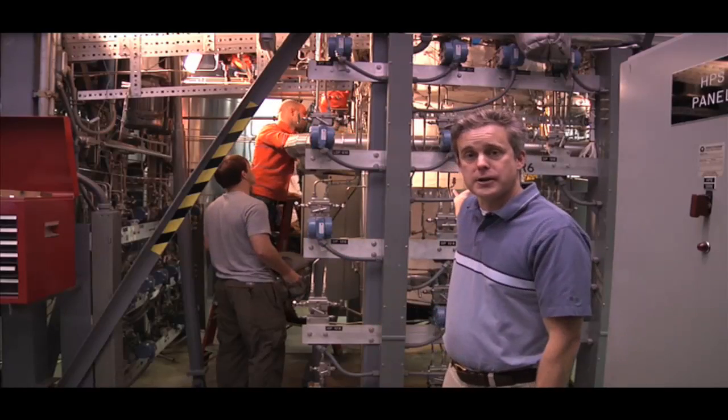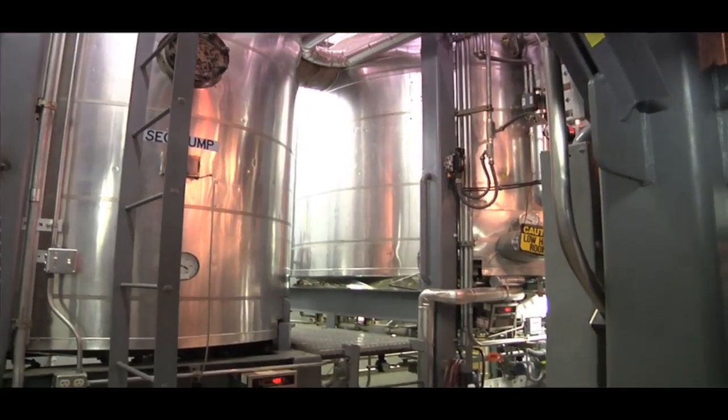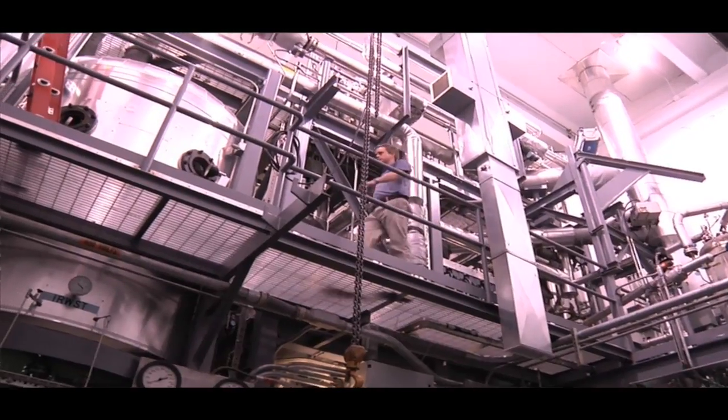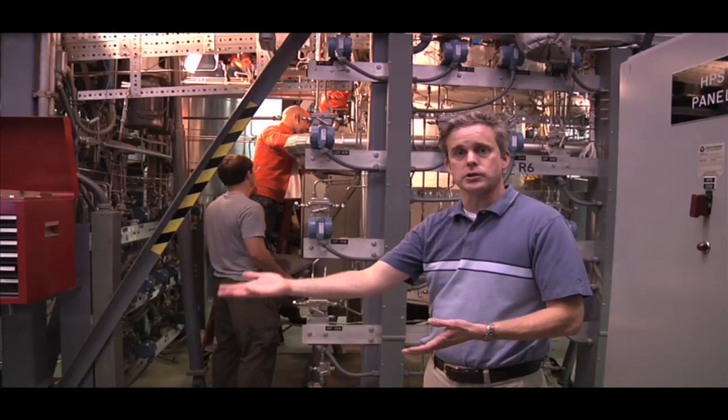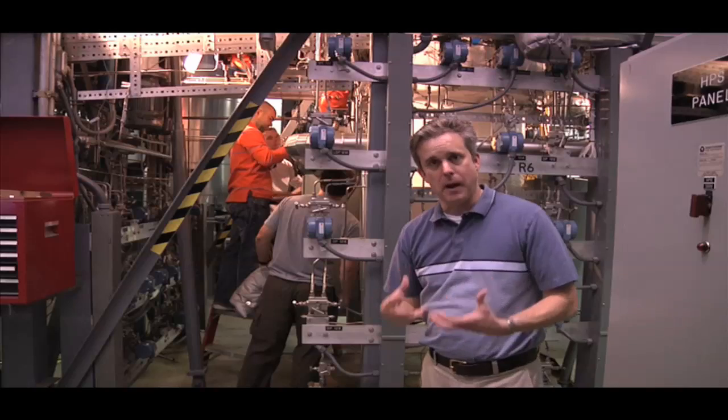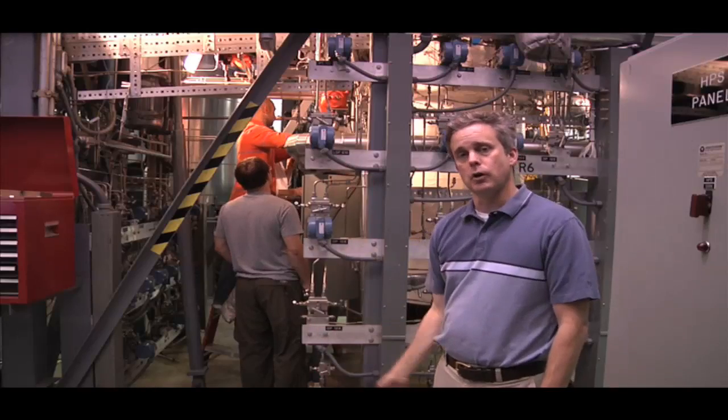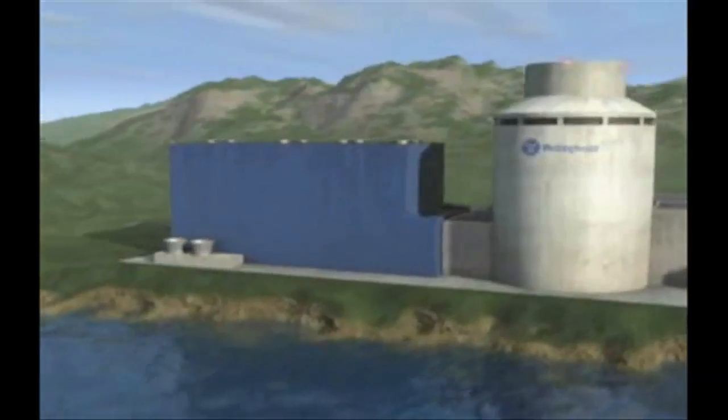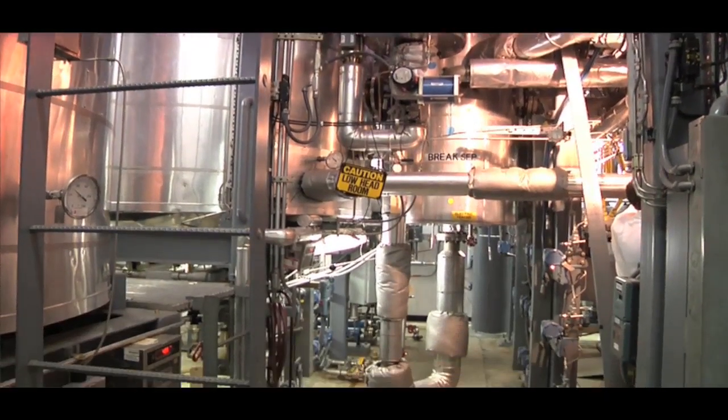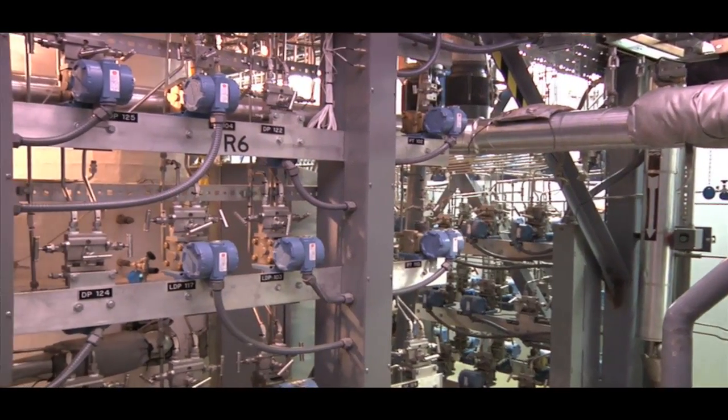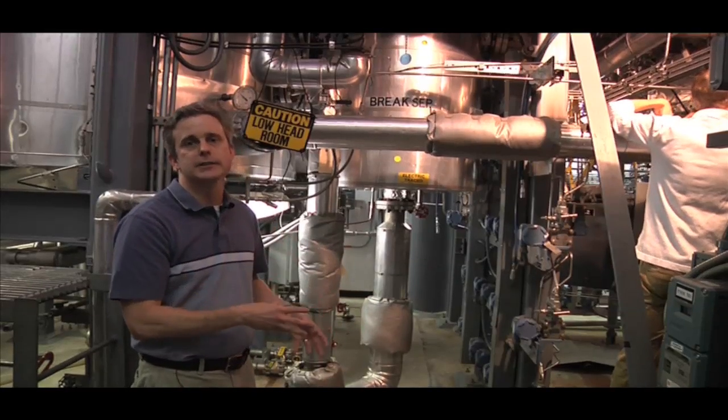What you really see behind me right here is, in essence, a scaled model. So you have the reactor vessel in our case. It's a pressure vessel, and it's electrically heated, no radioactive material. You have two reactor cooling pumps on either side. You have what we call a hot leg and a cold leg. We have what we call a steam generator above my head. This is where you generate the steam. In a real nuclear power plant, that steam that's generated would be used to generate electricity by turning some electrical turbines. However, in our case, we're not really here to generate power, but rather we're here to do research. So the steam we generate, we actually send out the ceiling of the building itself. But it basically models all the features that you would see in AP1000, albeit at a much smaller scale. You'll see a number of different instruments. We have pressure instruments, temperature instruments, flow instruments, and basically all the different parameters that are part of this facility, we try to measure. And that's really what our job is, to really understand in very fine detail what's happening.